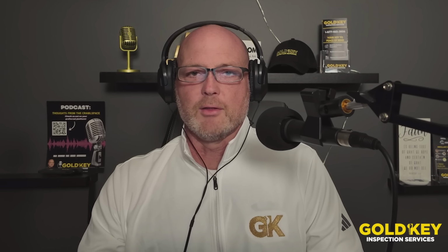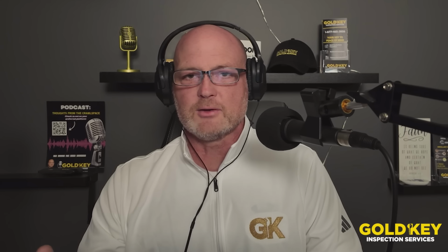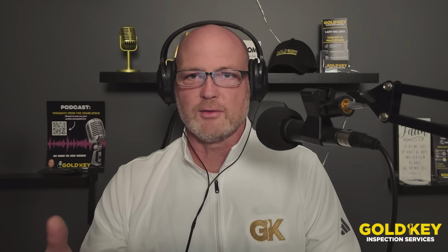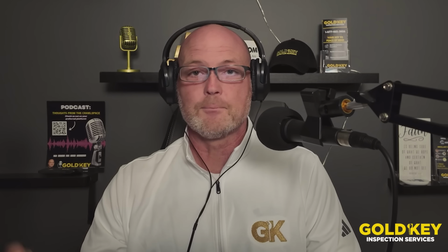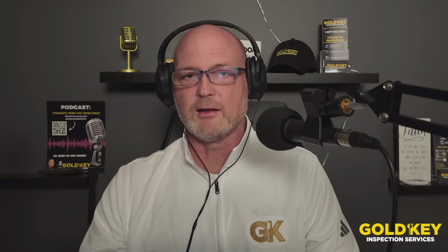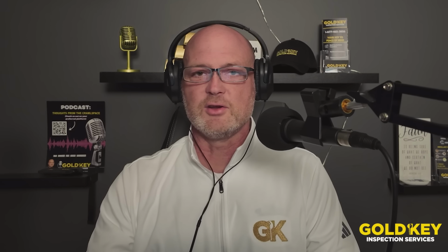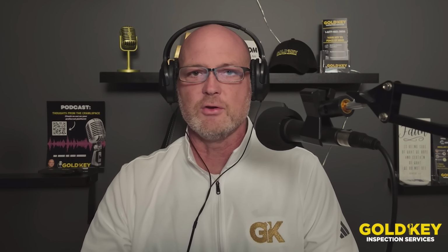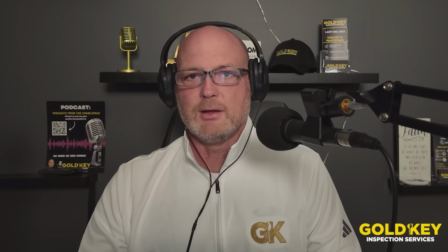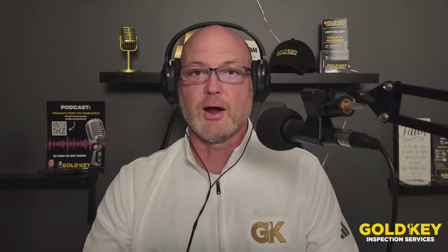So there's no problems with injury or getting electrocuted or the unit kicking on because somebody turns a breaker on that they saw was off or whatever. He needs to have total control of that, and that electrical disconnect is usually just a pull-out breaker or fuse that he can just plop right back in there when he is done. So we're definitely looking for that. It's pretty rare nowadays to see one without it, but occasionally you are surprised.